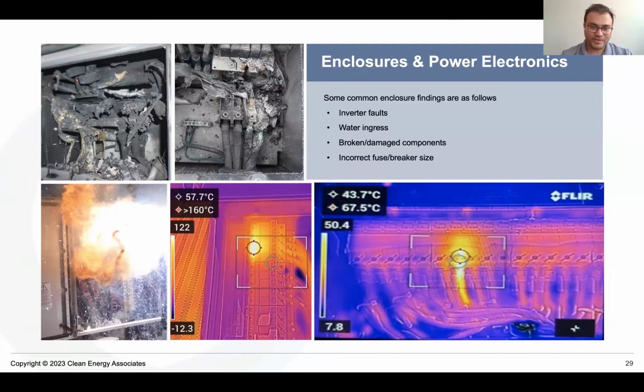Apart from loose screws, I've seen technicians on site stripping off wires right above the terminal blocks. When they do that, small copper strands go inside the terminal blocks, and we've seen a thermal event occur from a small copper strand that went inside a terminal block. Simple best practices, like don't strip your cables right over the terminal blocks, are important. You may not notice the effects right when you're doing the work, but it can cause a major fire.